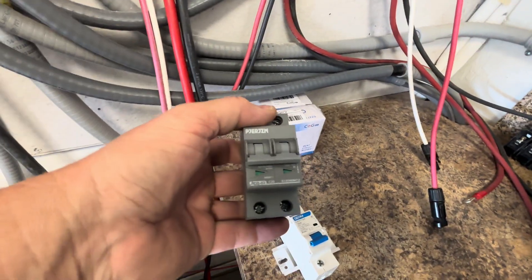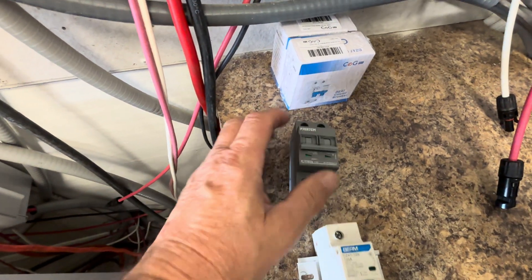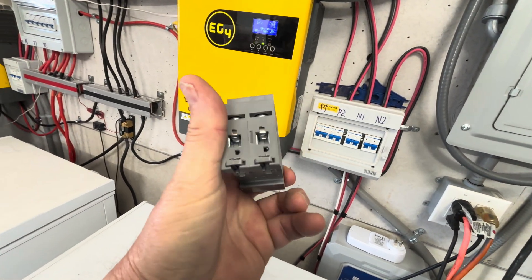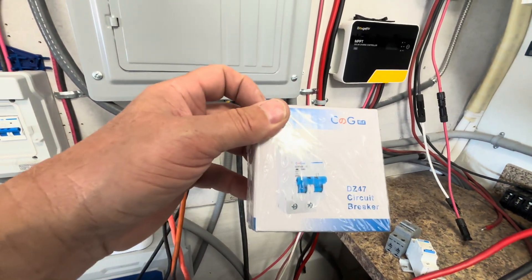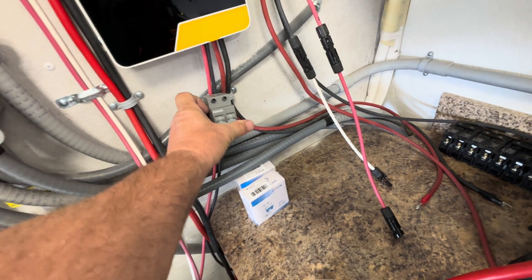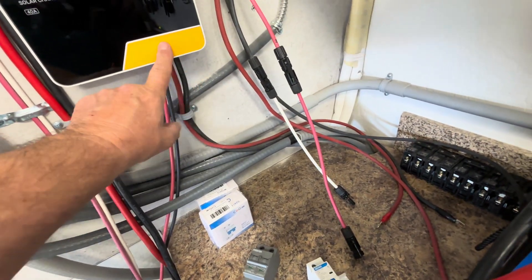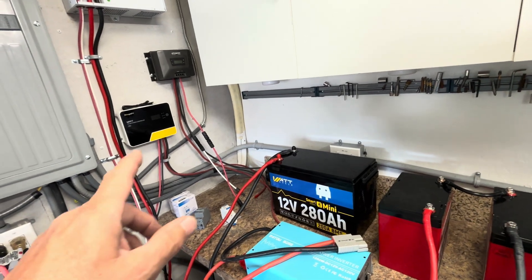Here's an example — this is a 20-amp double-pole breaker. You put the positive in on one side and negative on the other, but watch out because they're not all positive-on-left and negative-on-right — you have to check what it says. This one isn't very clearly marked, but another brand I have was clearly marked. Put one of these for your solar going into your charge controller, and one on your battery cable so you can shut off power from both the solar panels and the battery.